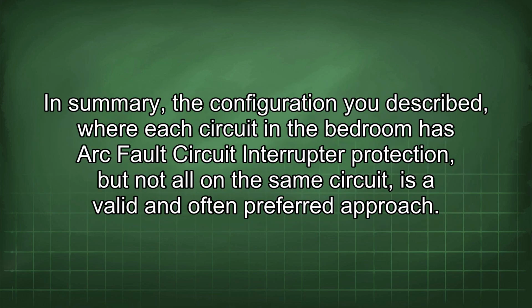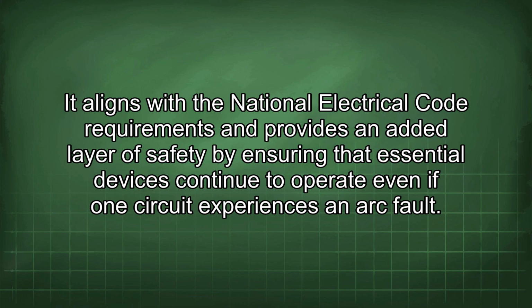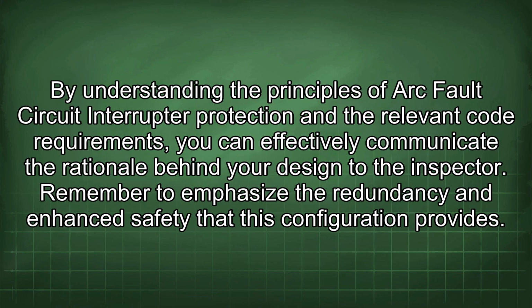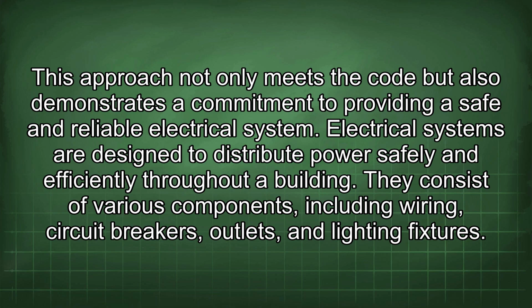In summary, the configuration you described, where each circuit in the bedroom has arc fault circuit interrupter protection, but not all on the same circuit, is a valid and often preferred approach. It aligns with the National Electrical Code requirements and provides an added layer of safety by ensuring that essential devices continue to operate even if one circuit experiences an arc fault. By understanding the principles of arc fault circuit interrupter protection and the relevant code requirements, you can effectively communicate the rationale behind your design to the inspector. Remember to emphasize the redundancy and enhanced safety that this configuration provides. This approach not only meets the code but also demonstrates a commitment to providing a safe and reliable electrical system.